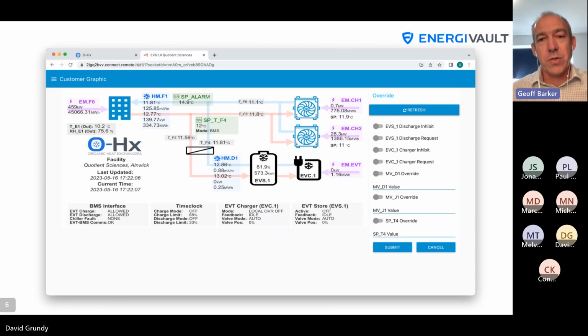On the other hand, the system can be set up so EnergiVault is the primary chiller. And in fact, we've done that in some tests recently, because at the early part of the year the demand was relatively low, a relatively modest demand, which allowed EnergiVault to satisfy all of the demand for several hours. So in that case, the BMS sees EnergiVault as the primary chiller number 1. So effectively, you're using the BMS to determine what sequence of chiller capacity is brought online, and whether it be the primary chillers or EnergiVault, and you can mix and match when that comes on.